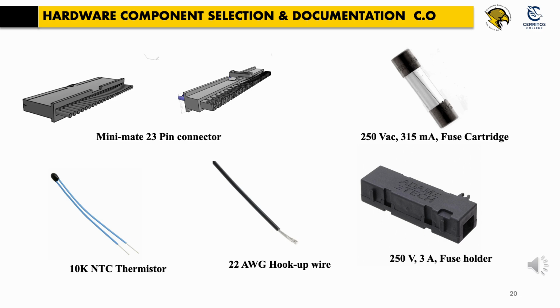For temperature sensing, we standardized on 10K NTC thermistors. We reviewed supplier data sheets to verify that the thermistors had the electrical isolation capability required by the design strategies. Choosing the right thermistor was essential because temperature is one of the key safety indicators monitored by the CSC boards. We also chose 22 gauge wiring for the cell sense lines and communication lines, offering the right balance of flexibility, insulation rating, current handling, and compatibility with mechanical routing clips.